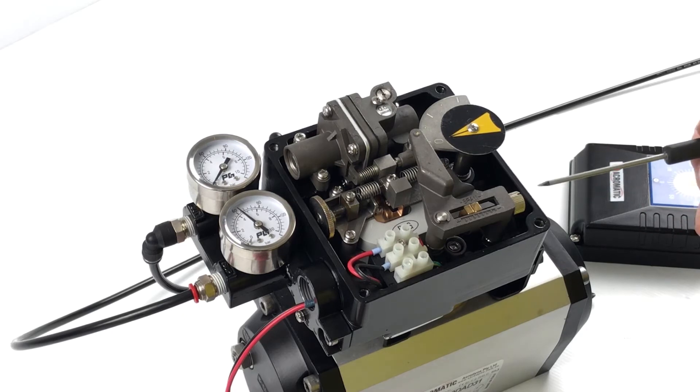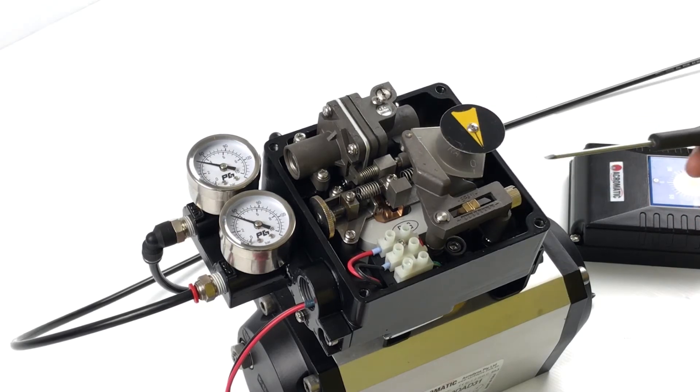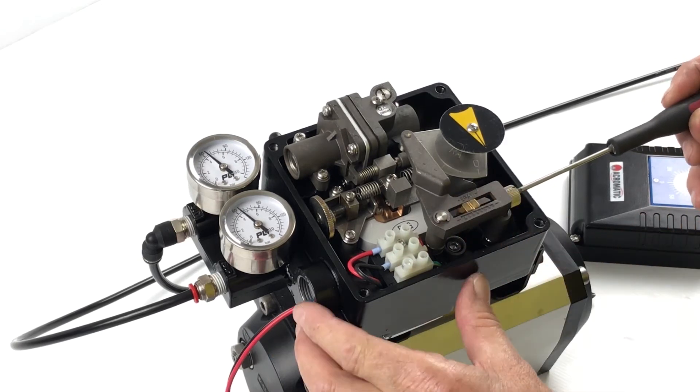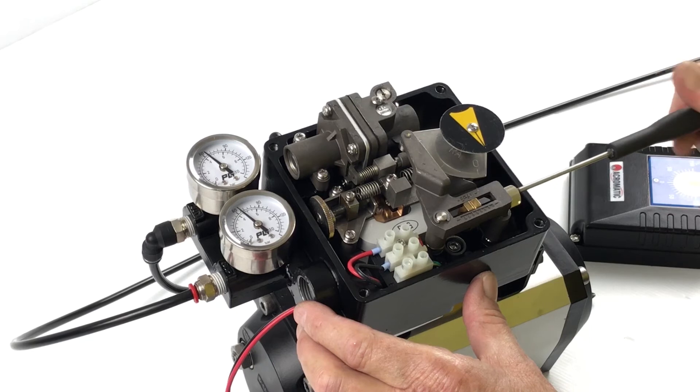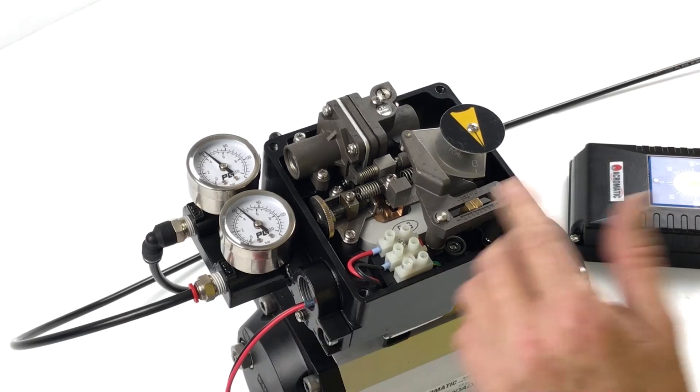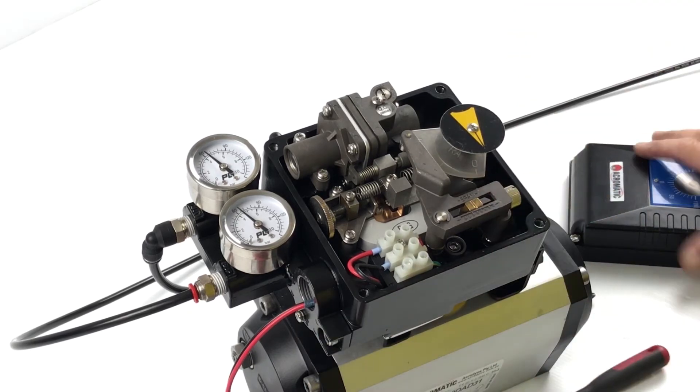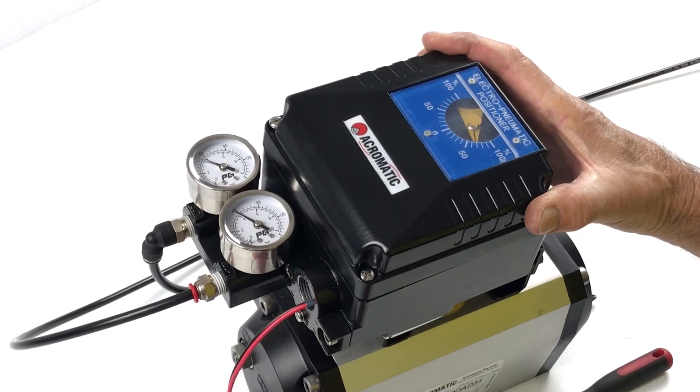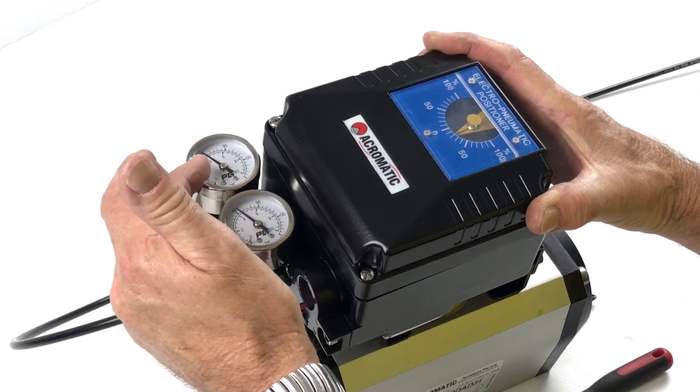So I'll go up to the top end and decrease the span by moving this towards the negative. You can see the indicator moving away. We've still got pressure on the gauge there.